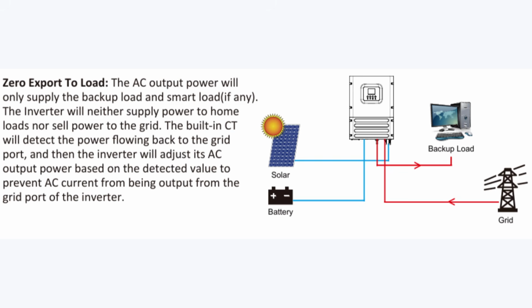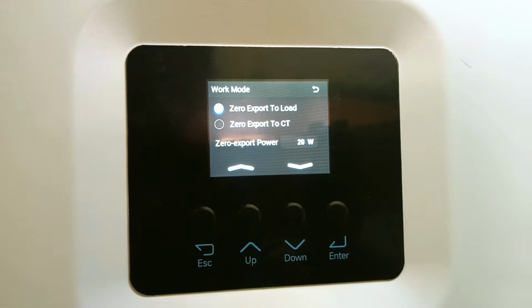And the manual says the AC output power will only supply the backup load and smart load, if any. The inverter will neither supply power to home loads nor sell power to the grid. The built-in CT will detect the power flowing back to the grid port, and then the inverter will adjust its AC output power based on the detected value to prevent AC current from being output from the grid port of the inverter. Next, we have 0 export to CT.